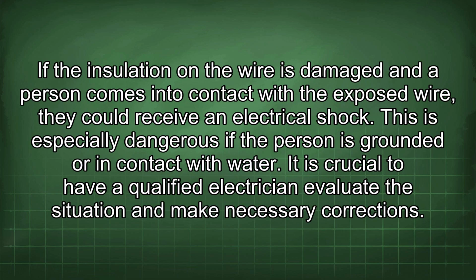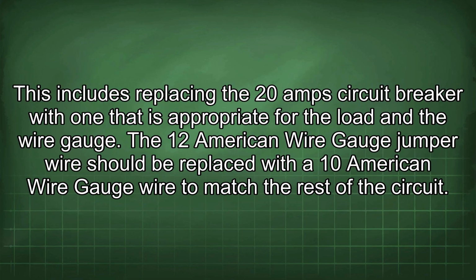If the insulation on the wire is damaged and a person comes into contact with the exposed wire, they could receive an electrical shock. This is especially dangerous if the person is grounded or in contact with water. It is crucial to have a qualified electrician evaluate the situation and make necessary corrections. This includes replacing the 20 amp circuit breaker with one that is appropriate for the load and the wire gauge.